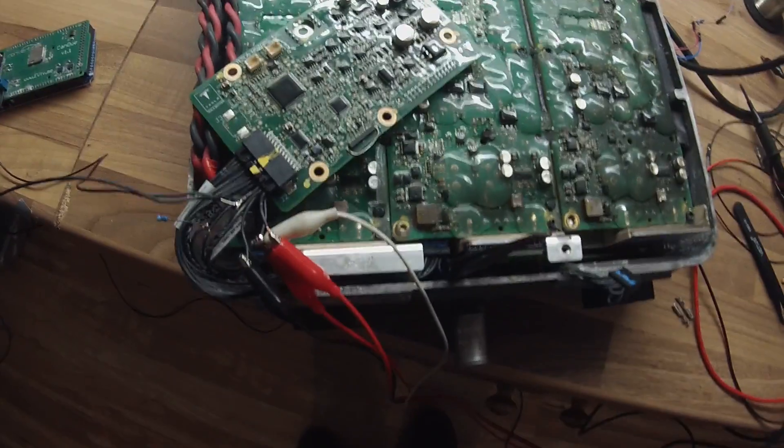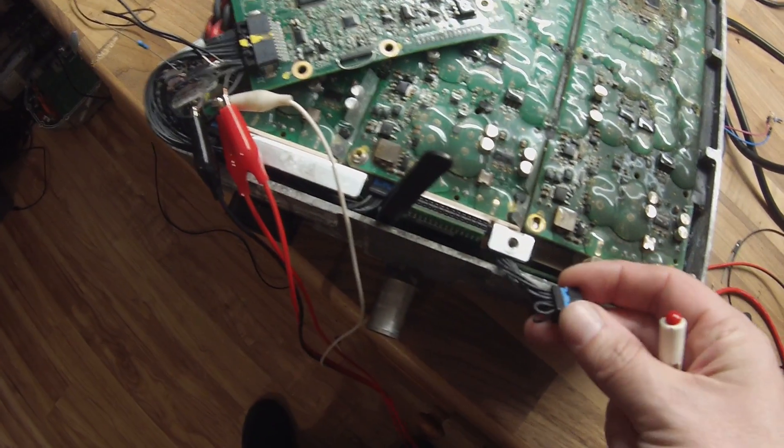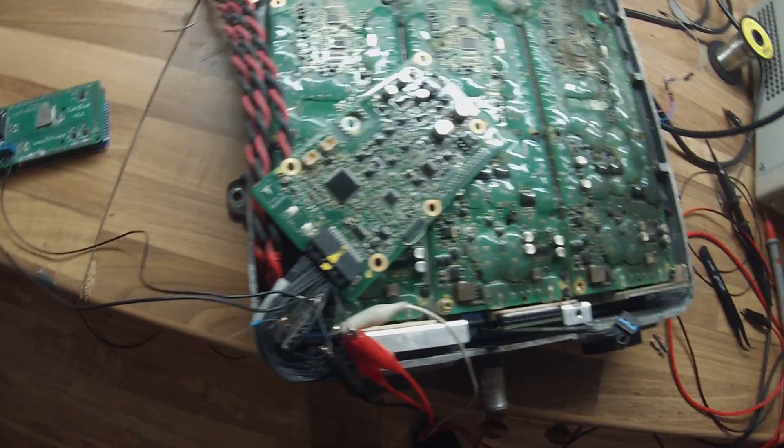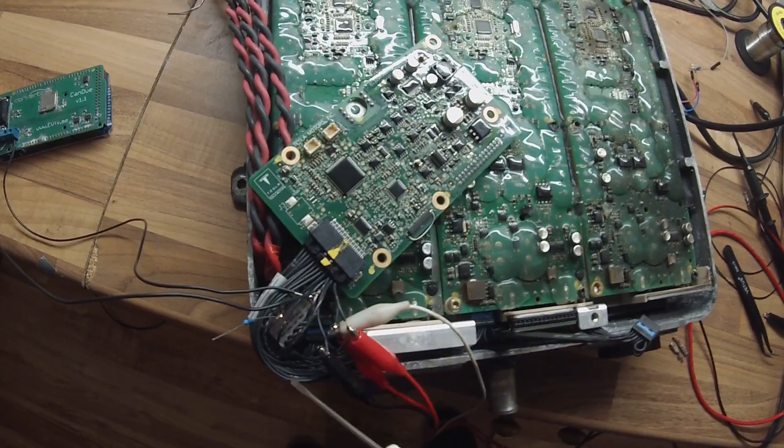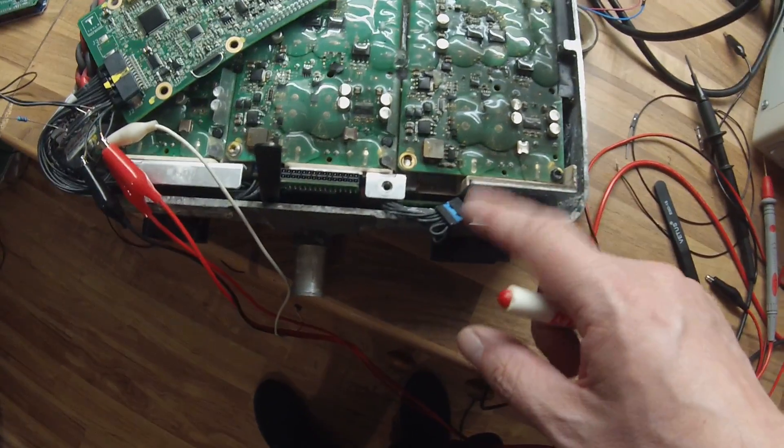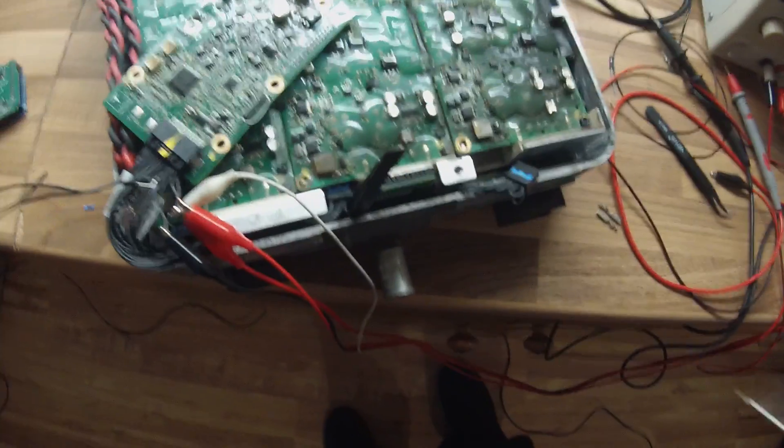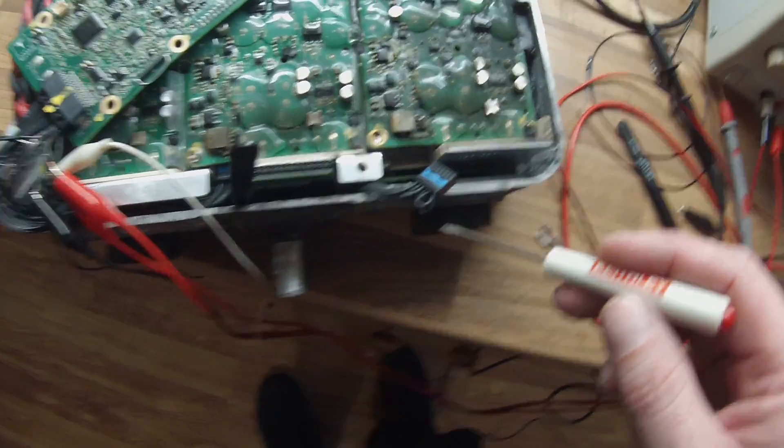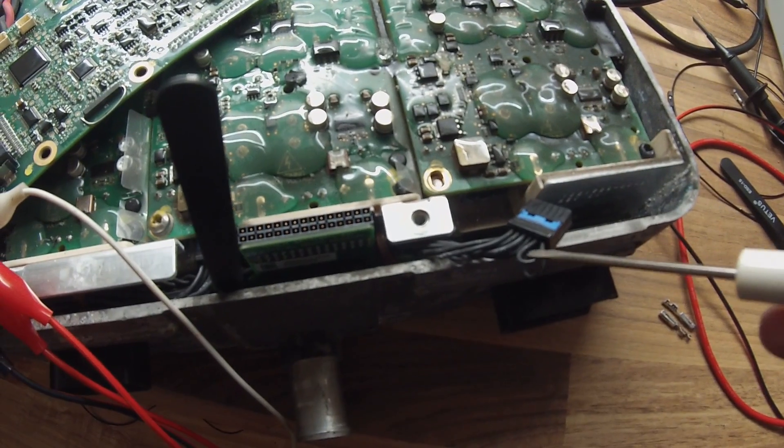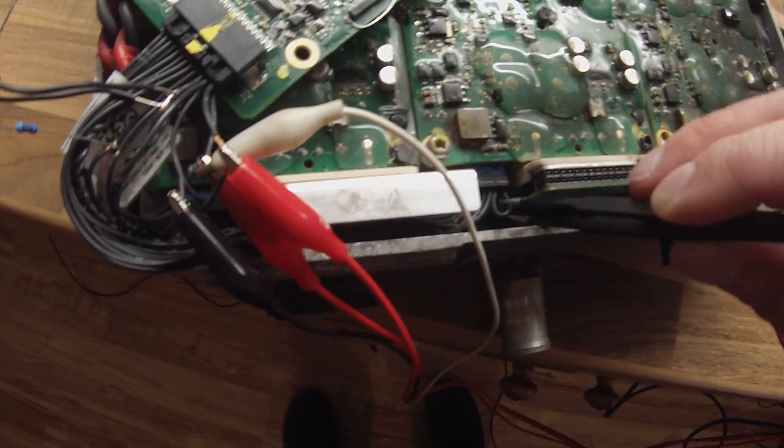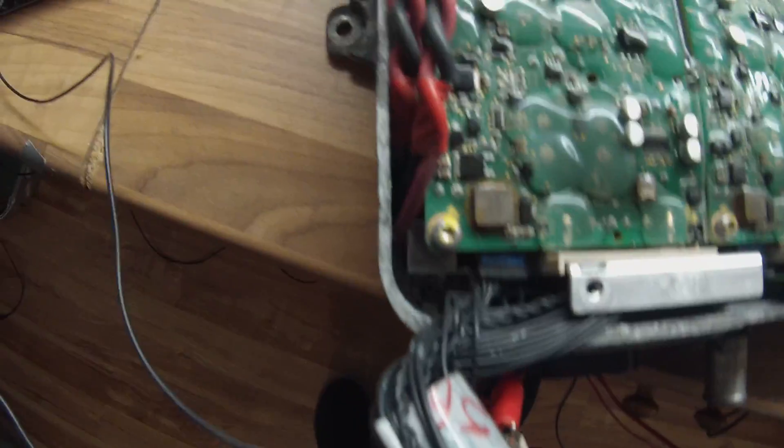that connects the signals from the logic board. This 24-way JST breaks down and gives us the three connection options to each of the power modules. Now each power module then has a selection of these shorting links. And for example, module 3 has got two links fitted. Module 2, I don't know if you'll be able to see this, but module 2 has got the top link fitted only. And we won't be able to see in here unless I get this out of the way, but module 1 has got the bottom link fitted.